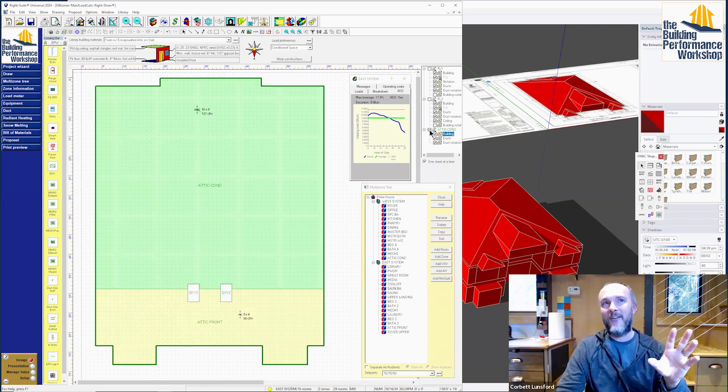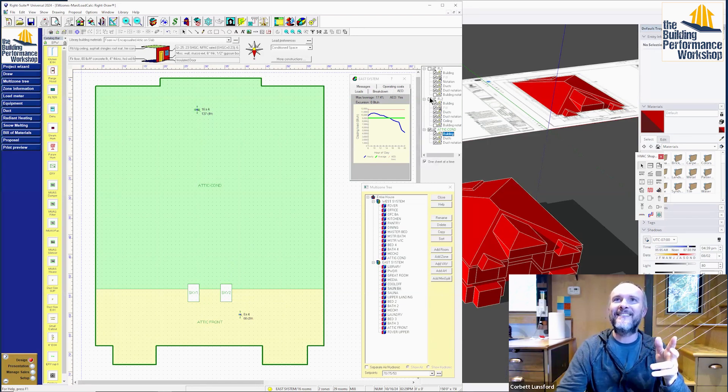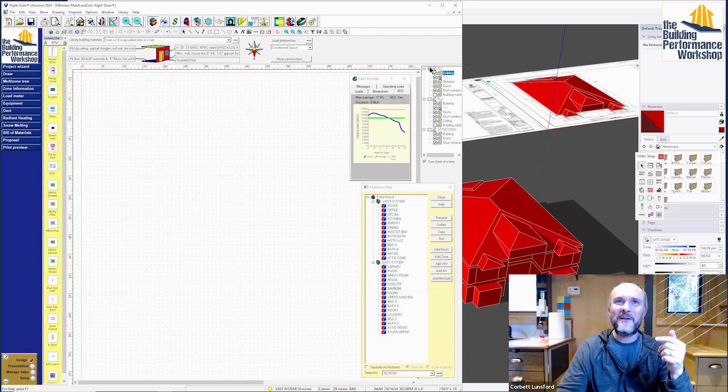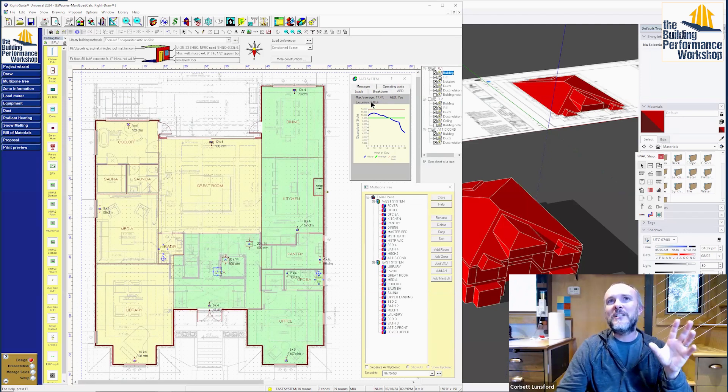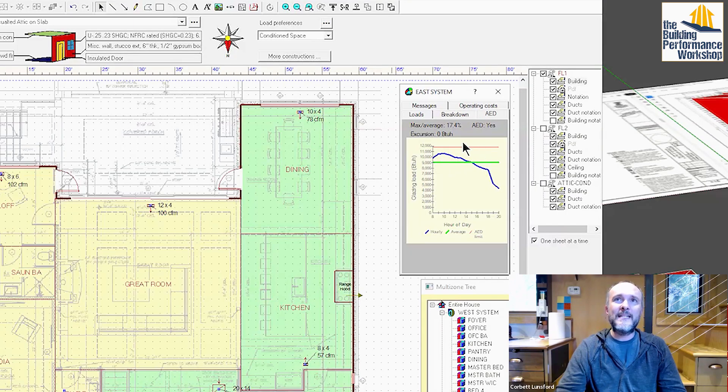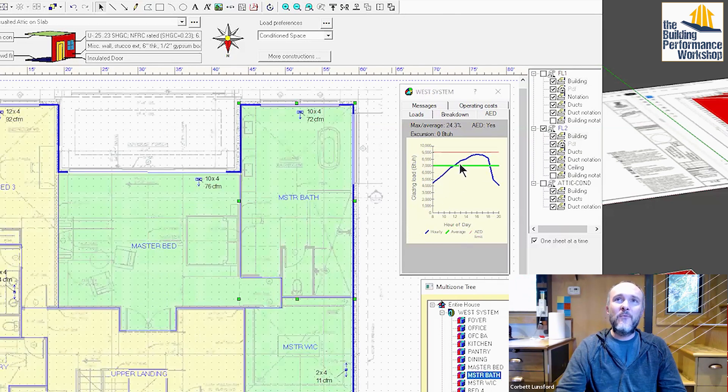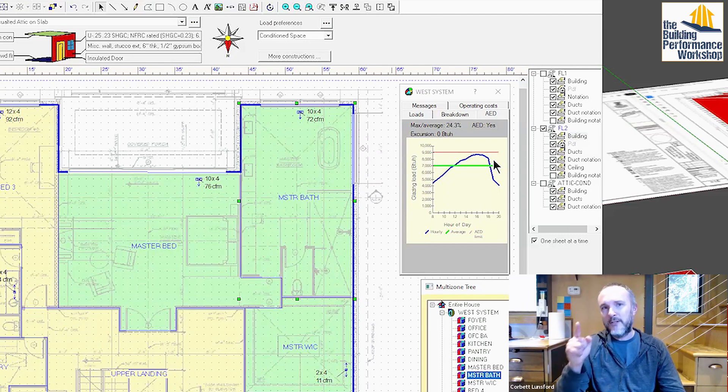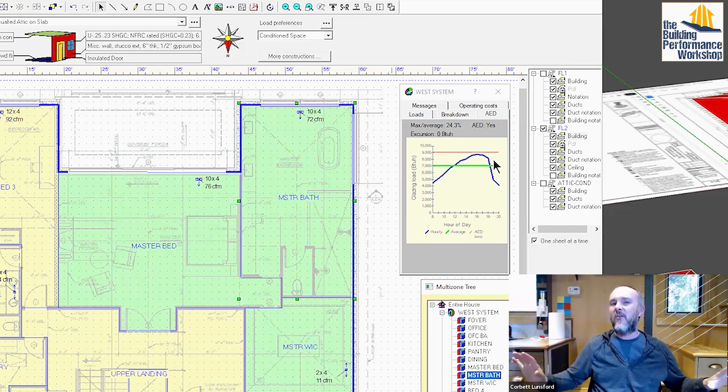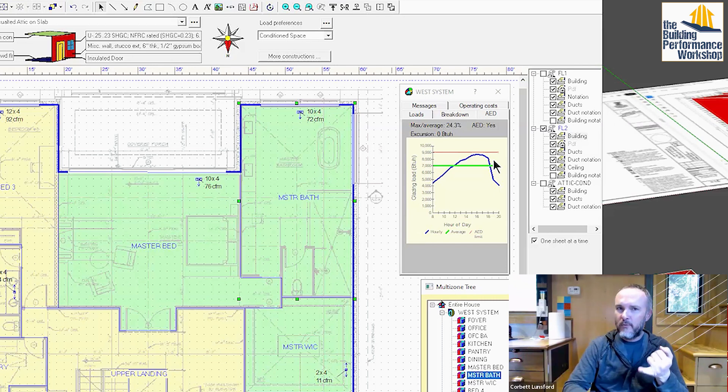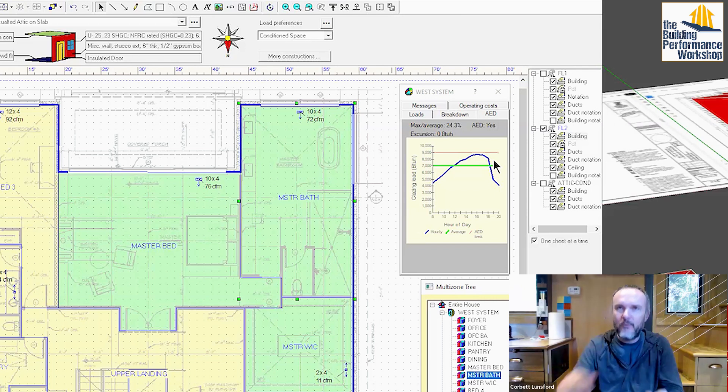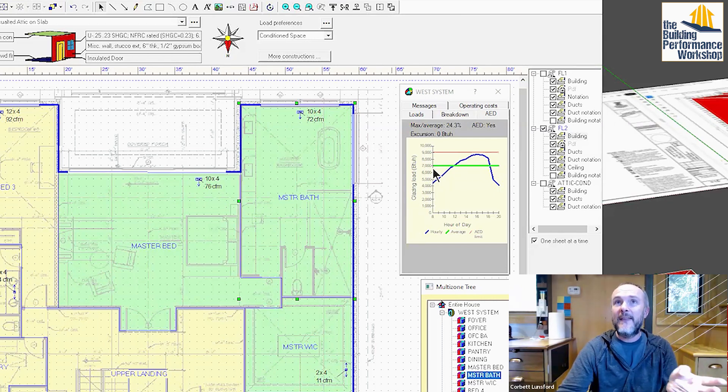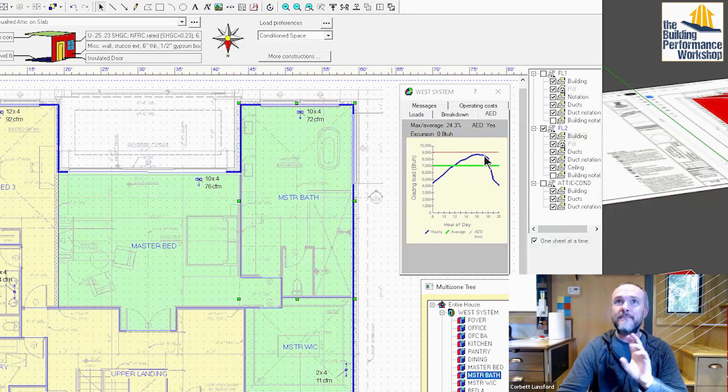You can see here that it peaks in the morning and then goes down throughout the day. That's the east side. The west side is low in the morning and peaks up toward the afternoon. By the way, what this graph always shows you with this AED graph is just about the windows. It's discounting all the other loads in the house, the loads through the walls and through the roof and through the floor. We're just honing down the windows, which is only part of the load. But this will have a big effect on how those rooms feel.